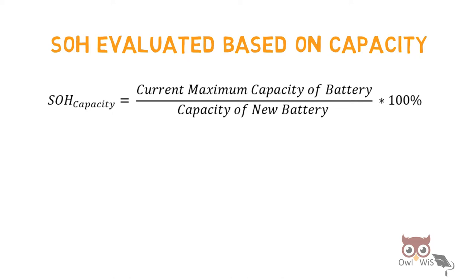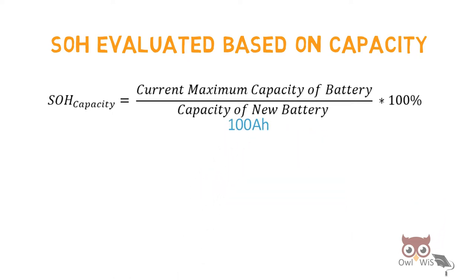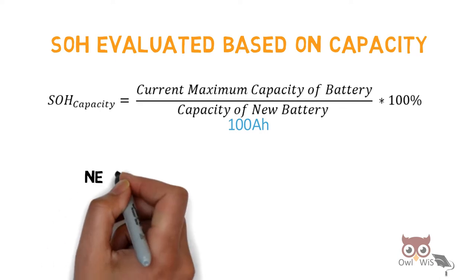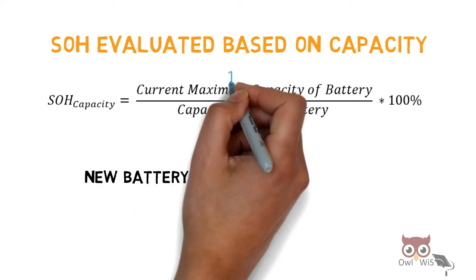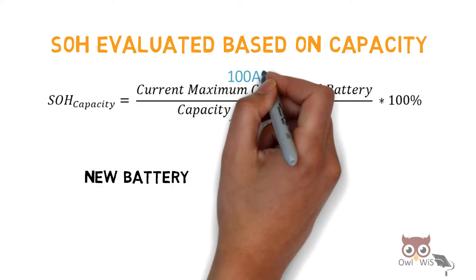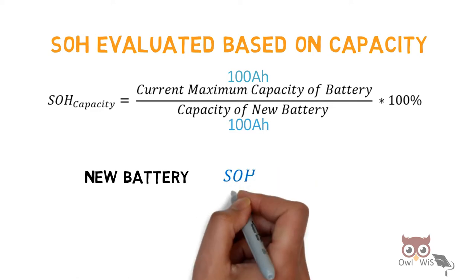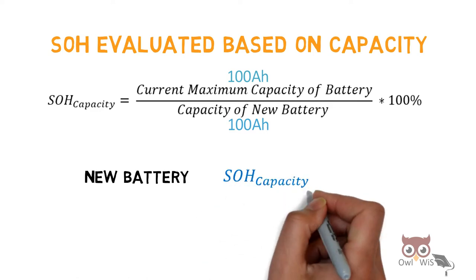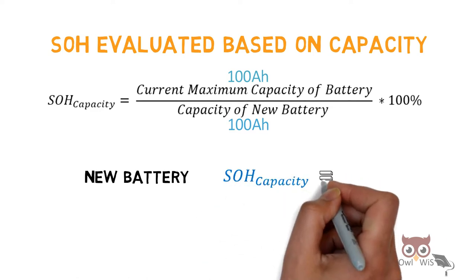For example, SOH evaluated based on capacity is the ratio of the current maximum capacity of the battery to the capacity of a new battery. If the capacity of a new battery is 100 ampere-hours and the current maximum capacity is also 100 ampere-hours, then the SOH capacity is 100%.